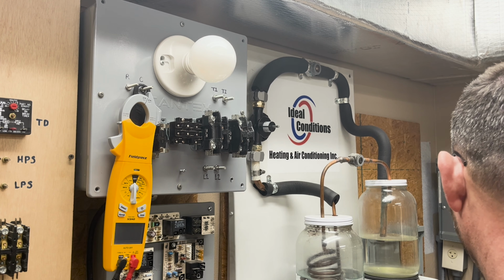That's how a one-pole contactor is more complicated than a two-pole contactor, because with a two-pole contactor you're breaking both legs of power. I want to give you a fair warning, because you could take a technician who thinks they're pretty savvy, throw a simple one-pole contactor at them, and they'll sit there and probably lose their cool if you're messing with them, because they'll realize they don't understand open and closed, and how one leg is always present no matter what.